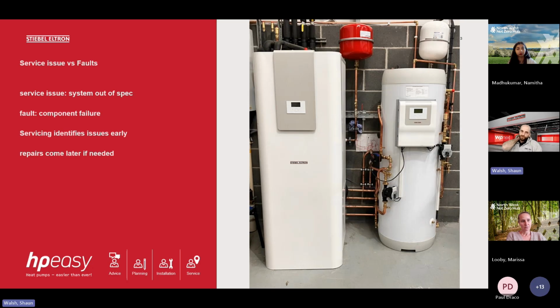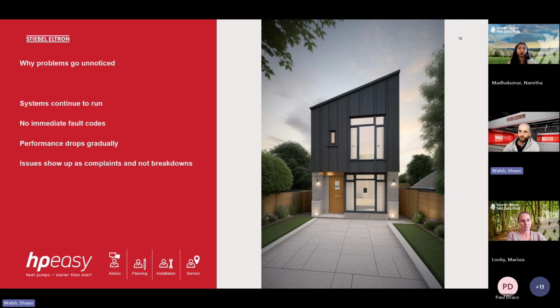Okay, so a lot of the problems that you'll see will largely go unnoticed for a long period of time if the system is not serviced and maintained. The reason is heat pump systems will continue to run even as the performance declines, because they are quite robust. They will run even if the system is not performing at maximum efficiency, and they very rarely just stop running. They're quite tolerant, so quite often you won't see immediate fault codes on the system.